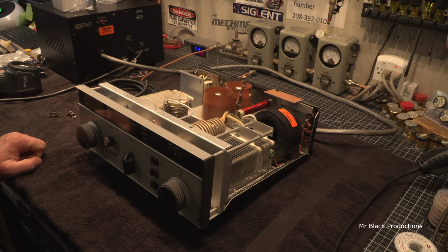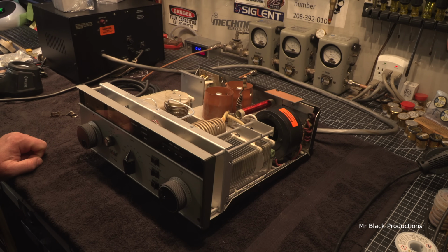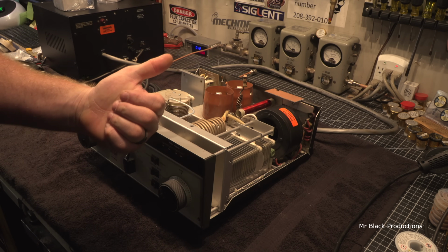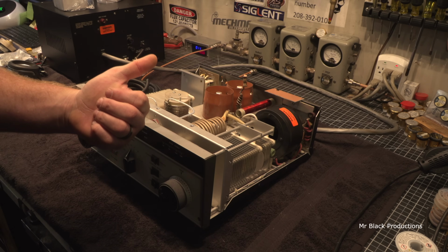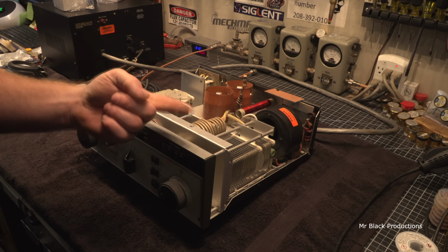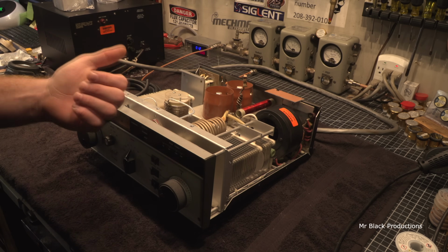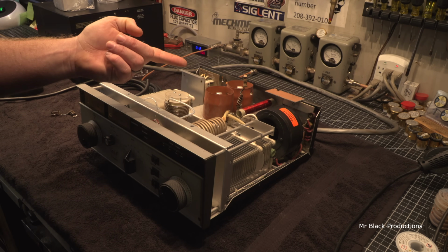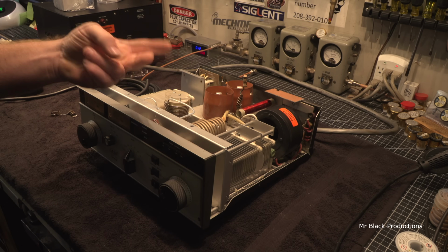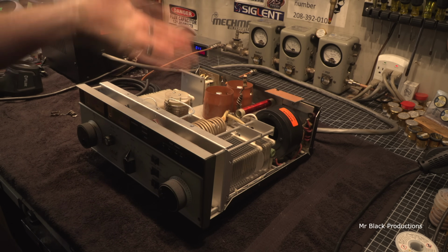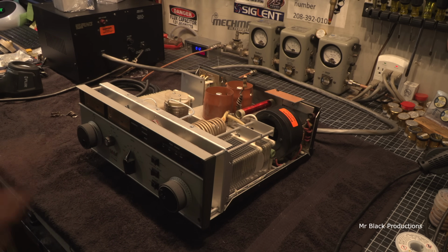The hardest part is going to be getting the high voltage on the tubes, and it's either going to pop as soon as we turn the high voltage on, which would indicate another problem, either in the tubes or the power supply, which I'm pretty sure is correct. So either it'll pop as soon as we turn it on, or as soon as we step on the foot pedal, it's going to go bang. We'll find out. Let's get this done, and we'll wait for that to bleed down to zero.